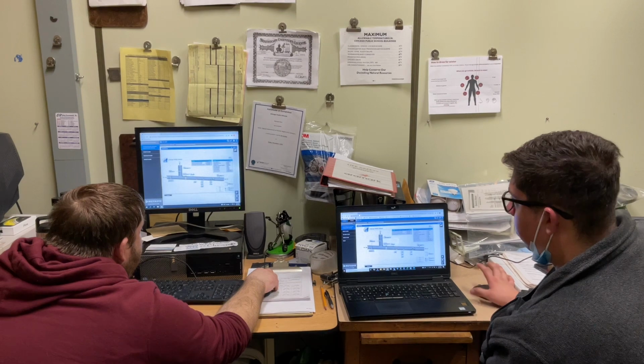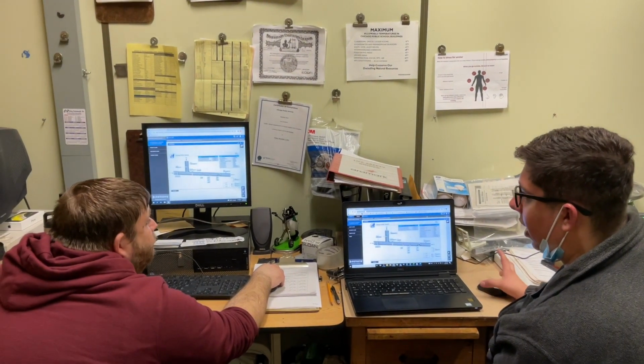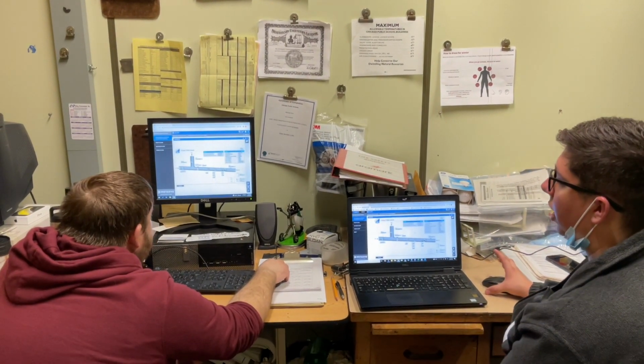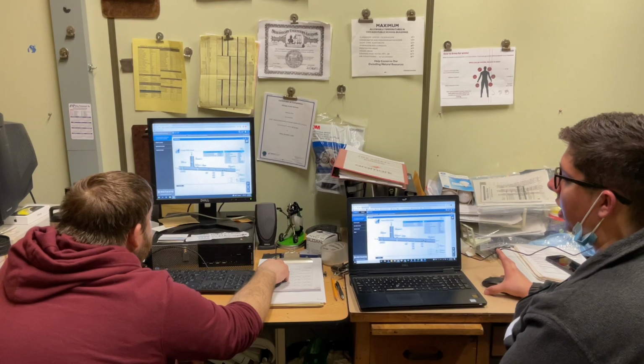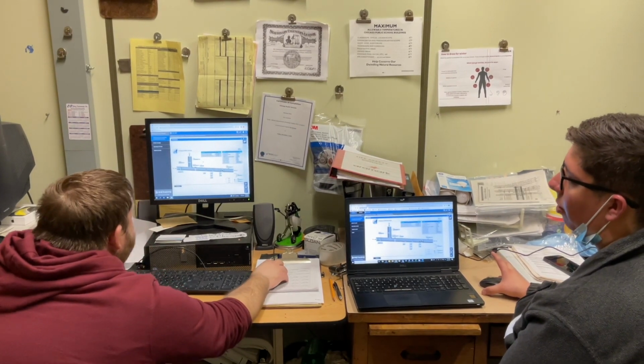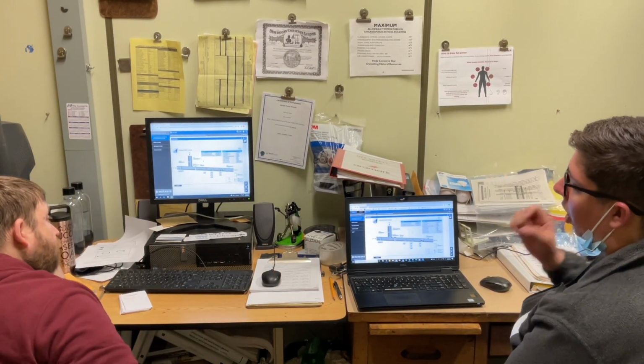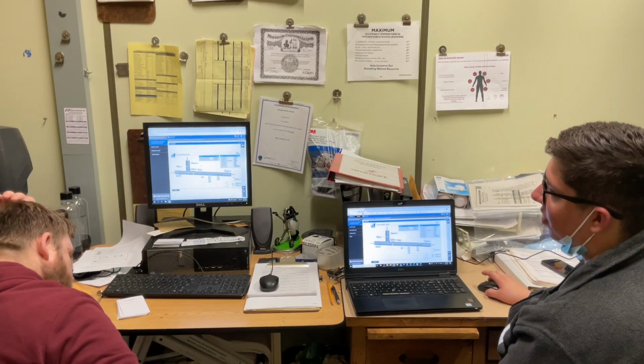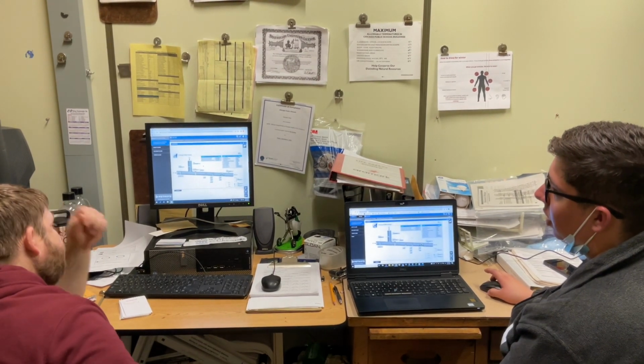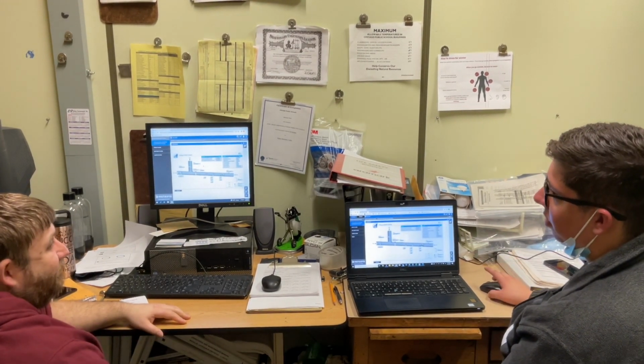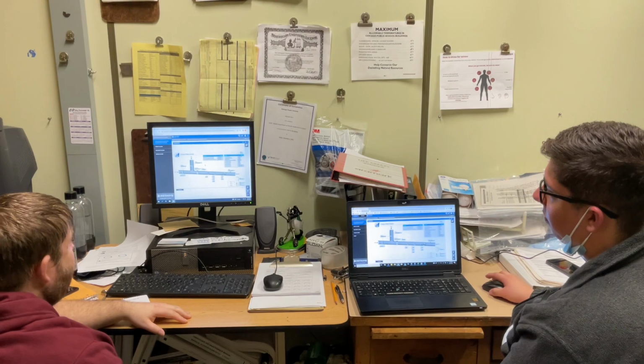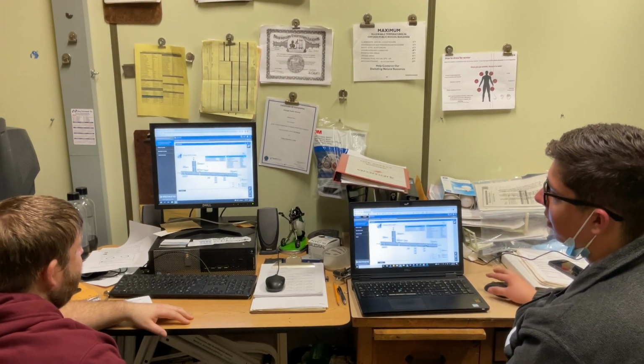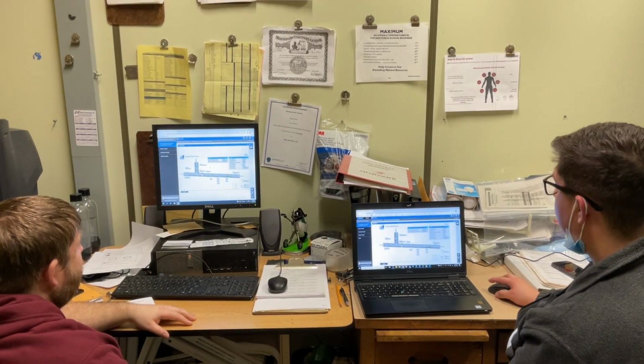So the sequence for these, it'll look at outside air and decide, based on what temperature it is outside, whether to bring in more or less outside air. So there'll always be that minimum that we've seen at 10%. They don't have a whole lot of movement on them. You've seen them. So sometimes you might have to dial that back just a little bit.